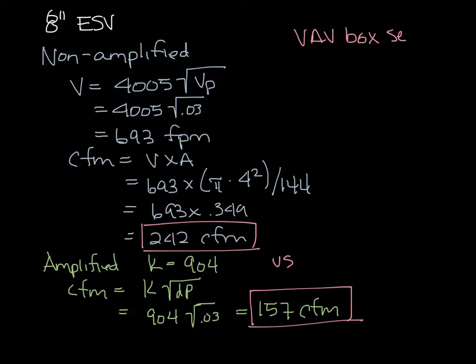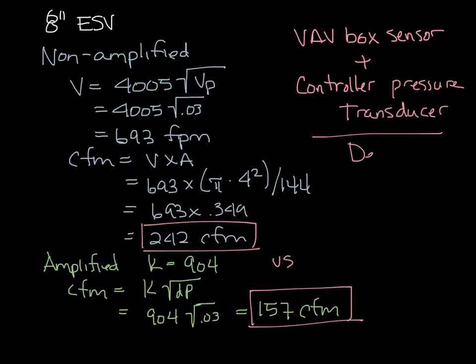It depends on the VAV box flow sensor and its amplification, and the control pressure transducer and how low it can read. So these two things determine the minimum controllable CFM of any given VAV box.